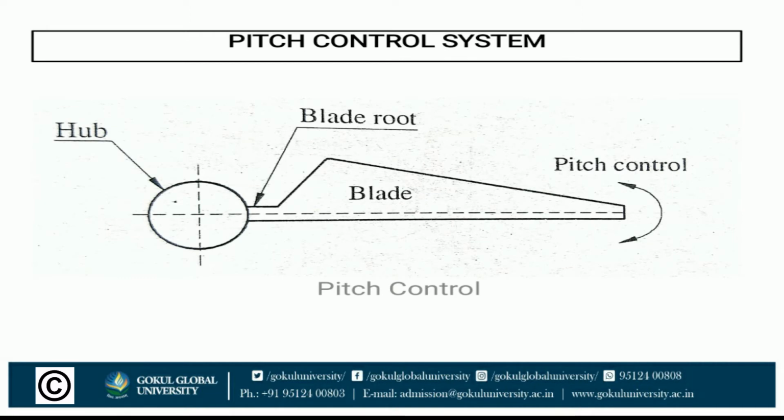It is the diagram of the pitch control system. The pitch of a blade is controlled by rotating it from its root, where it is connected to the hub. The pitch control mechanism is provided through the hub of the rotor using a hydraulic jack in the nacelle. The controller continuously adjusts the pitch to obtain the optimum performance. Thereby, the power and speed of the wind turbine shaft is adjusted to match with the generator speed and its electrical output.